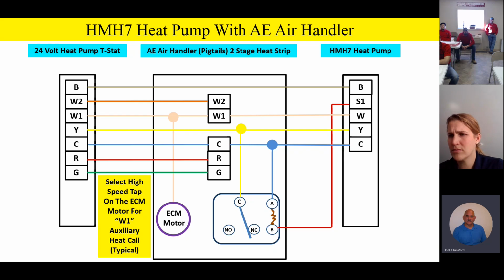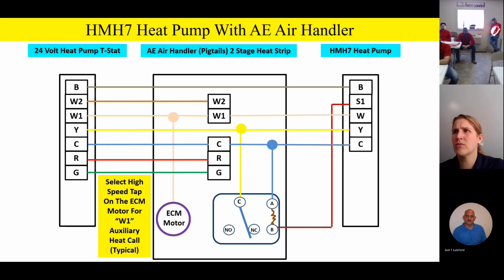Now remember, guys, on an ECM motor, any kind of ECM motor, those high efficiency motors, they've got speed taps on them. In this case, they just have speed taps that you can change. But remember, if it has more than one speed command going to that motor, which it could have on a heat pump, you could have a low airflow command, and then all of a sudden you're going to have an auxiliary heat command, for instance. If that's the case, any ECM motor with more than one speed command is just going to drive that motor to the highest speed command that it's receiving. That's an important thing we have to remember about all ECM motors. And ECM is just a fancy name for the high efficiency motor. It's an electronically commutated motor. That's what ECM means. But if you have multiple speed taps on it, it'll just automatically go to the highest speed command that it's receiving. So this is why we can have multiple taps on this motor, and it doesn't hurt it to have more than one speed command. So that's pretty cool.